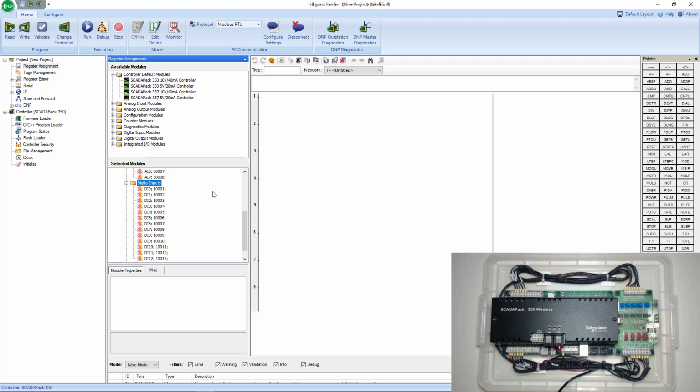Next, you have your digital inputs. So we are using DIO0 as a DI. So we got to make sure that we write this down. DIO0 is 10,001. We also use the next 3 as well. So DI1 is 10,002, DI2 is 10,003, and DI3 is 10,004. So I want to make sure we write those down because we are using our DIOs as DIs, especially the first 4. And then you have your analog outputs if you care to use those, as well as DOs. So we know that DIO0 is a DI, DIO1 is a DI, DIO2 is a DI, and DIO3 is a DI. So we could just ignore those. One thing we want to write down is DO4, or what we would call DIO4. We're going to use as a DO, so we want to make sure that we write down register 5 as well.